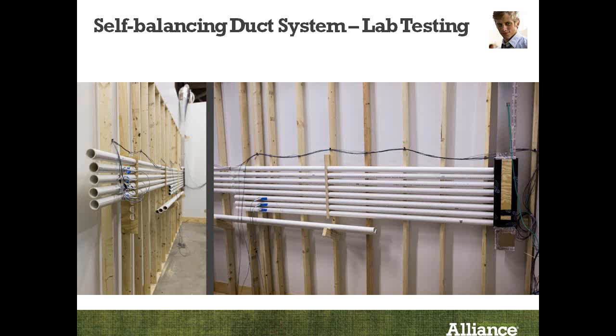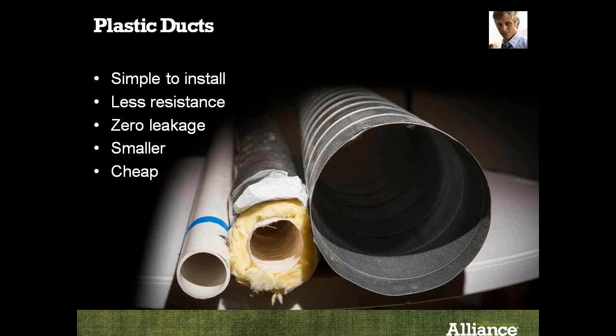And so you can see here's just a quick snapshot from our lab, some of the testing that we're doing. You can see on the left here that we've done a case where some of the duct runs are twice as long as the other runs, and even in this case, the airflow is very similar. We saw a deviation of less than 10% between those two different duct runs, which shows the system really has a lot of promise.